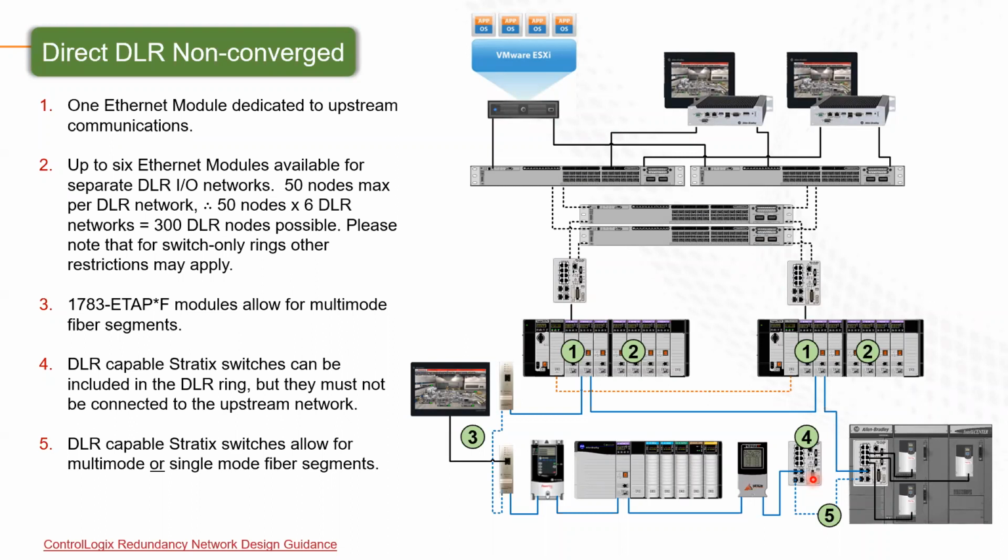And what we see quite often is our connections to our MCCs. Now, quite often we engineer this specifically. What we would want to do is put a switch on the end of the MCC run, because everything in the MCC is going to be a star or linear type topology. So if we want to add it to the ring, we generally will hang a switch off the side of it that will handle, in this case, probably a VLAN specifically for the MCC, and use a 5700 to connect to the rest of the ring.